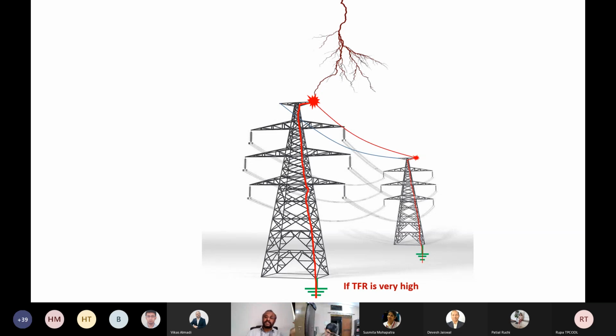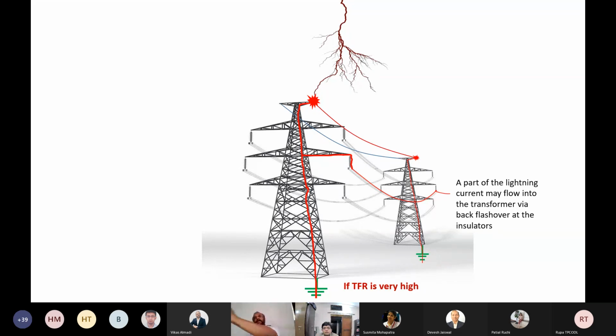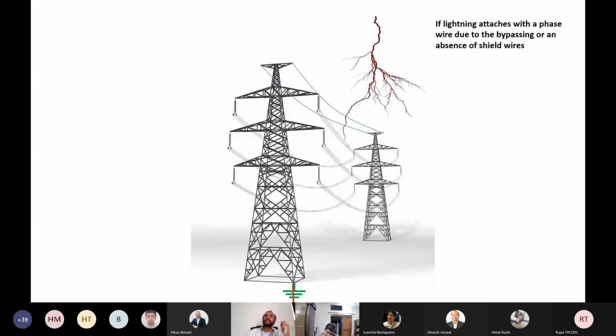this may happen, so that there will be flashover across the insulators, and the current passes into the live wires, which are connected in turn to the transformer. So we call it the back flashover, because the flashover happens from the earth side, the grounded side, to the live or, under normal circumstances, high voltage side. And this is one major mode of lightning current entering a transformer.